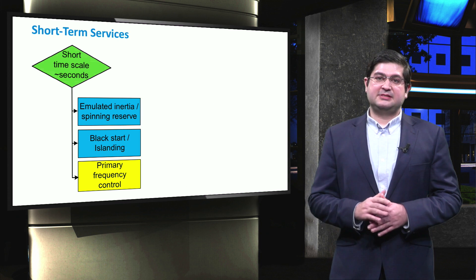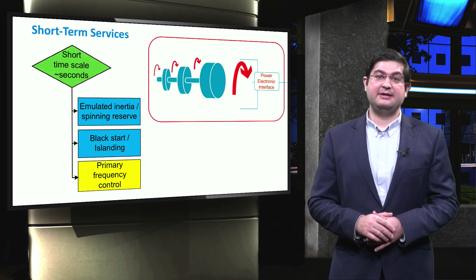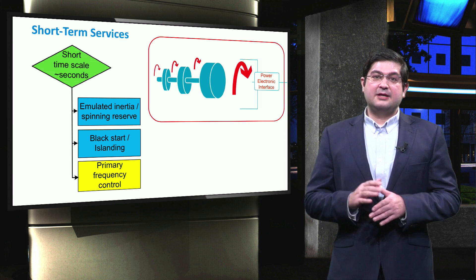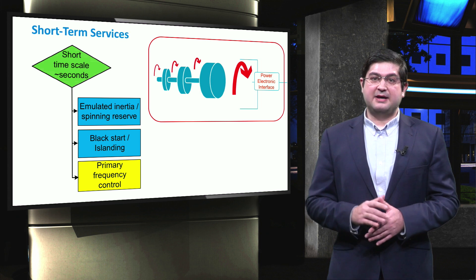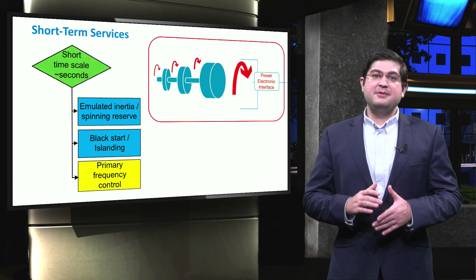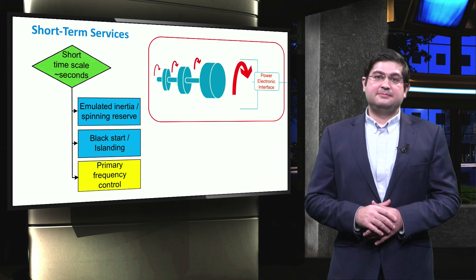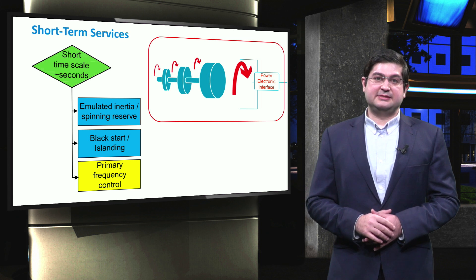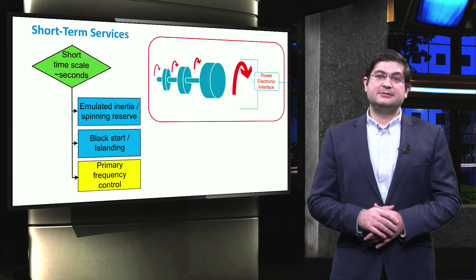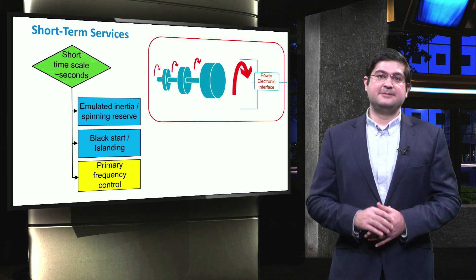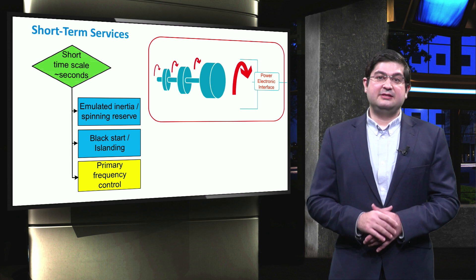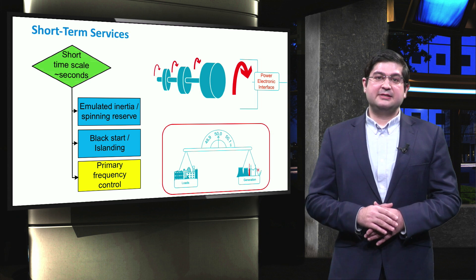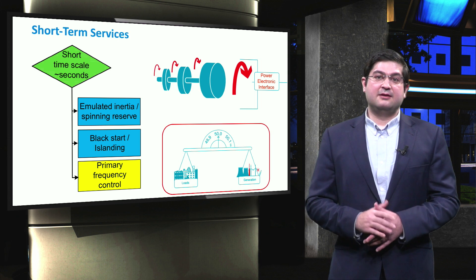Within a short time, like several seconds, units with rotating mass can provide inertial support, which releases the kinetic energy stored in the shaft of the unit. Though electronically interfaced units do not have any rotating mass, they can provide inertial support by emulating the behavior of the rotor. Another short-term service within the context of microgrids is islanding and black start. Note that in traditional power systems the black start may take up to several hours; however, in microgrids it can be conducted fast, even within several seconds. The most commonly known service is primary frequency control, which intends to suppress frequency deviation right after a contingency event like the outage of one unit.